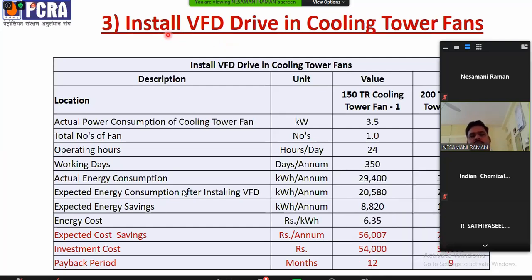The third technology, or emerging technology, is installing a VFD drive for cooling tower fans. Most chemical industries have a cooling tower for chillers or for other process requirements. The cooling tower fans will be constantly running. This is a case study about one of the energy audits which we have conducted, where we observed that the cooling tower fan was continuously running irrespective of the temperatures.